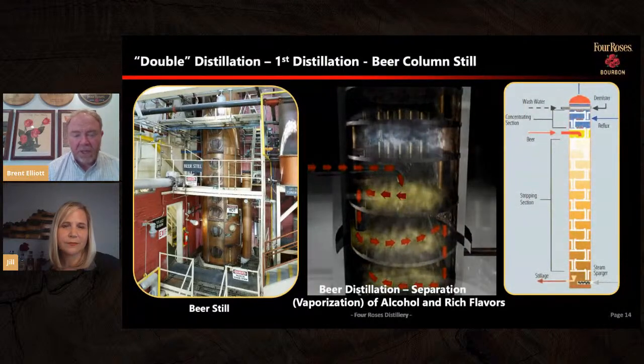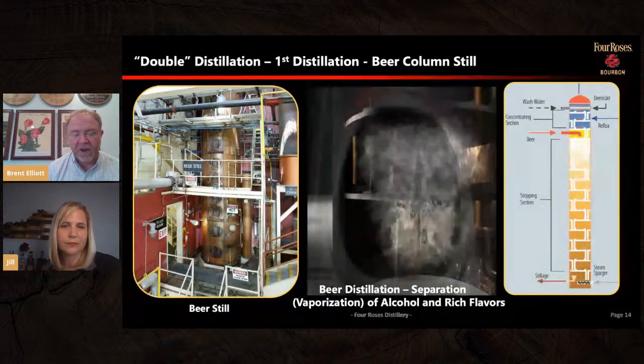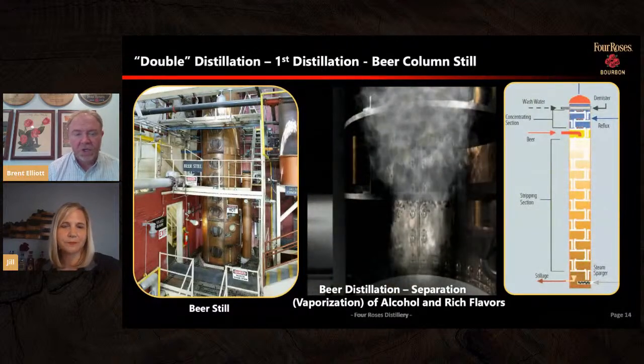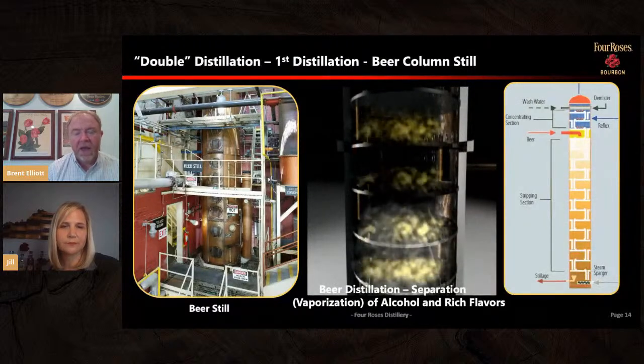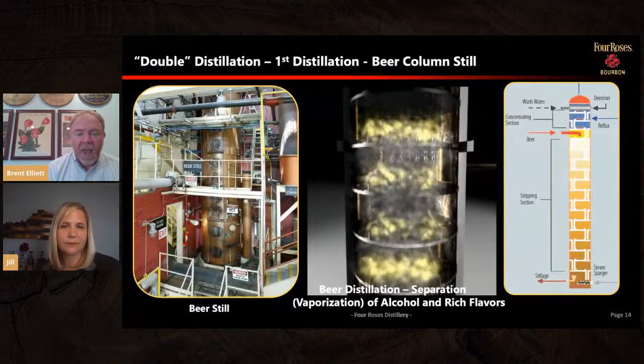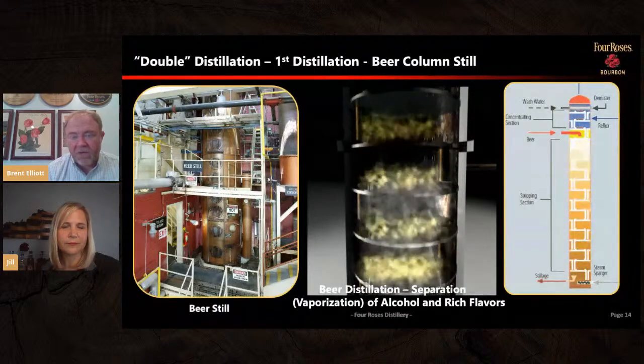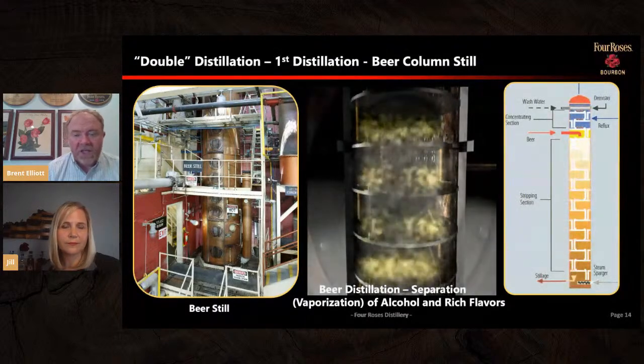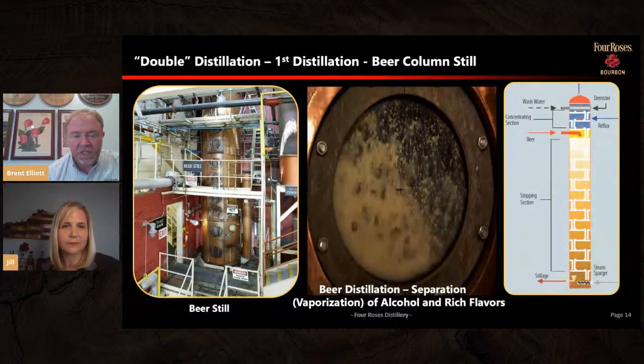And when that fermentation is complete, something else happens too. At the beginning, we set it at 67 degrees Fahrenheit. Then the yeast starts to metabolize, consume the sugars, and create energy, heat, alcohol and congeners. As it does this, the temperature rises in the beer. Once the temperature reaches 90 degrees Fahrenheit, which usually happens within 48 hours, we intentionally turn on a chilled water system. There's a coil inside each fermenter that we start up to maintain that temperature at 90 degrees through the remainder of fermentation.